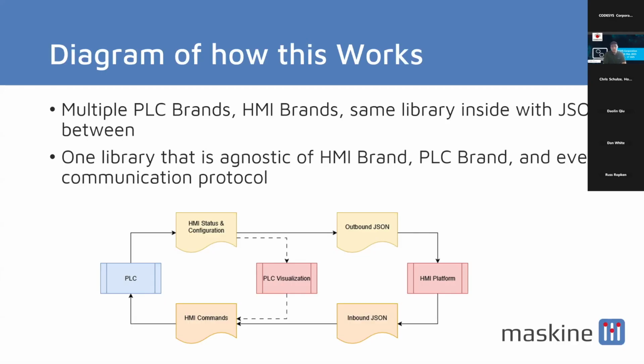In order to make the PLC library agnostic of the hardware, we've added those methods and properties to assign raw values and handle all the hardware aspects of it. That way, whether it comes in over Modbus, Ethernet IP, Ethercat, or standard digital I/O, we can handle the I/O without editing the base library. It makes a very, very clean and hardware agnostic system. So here's the code in action.